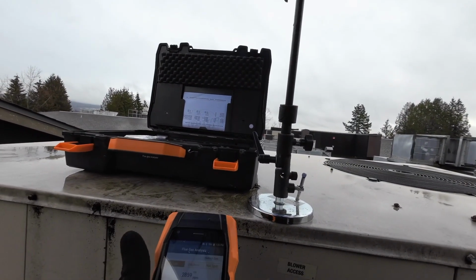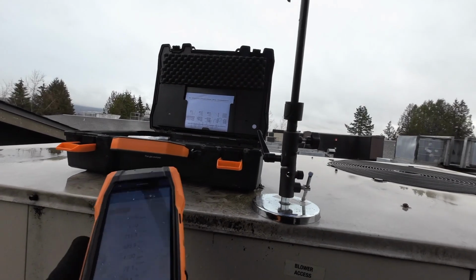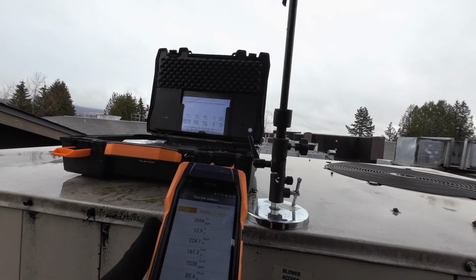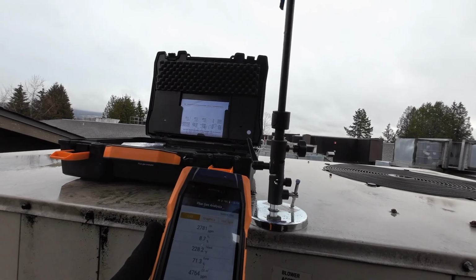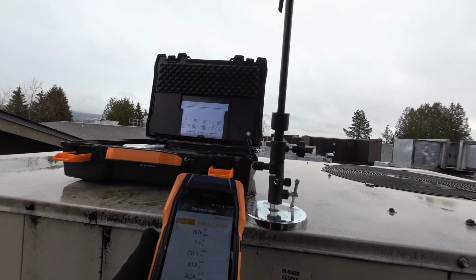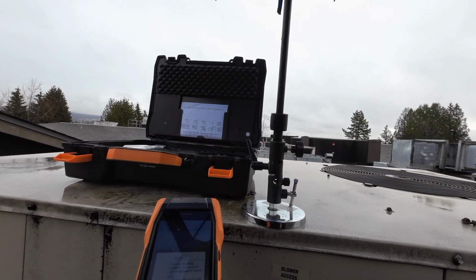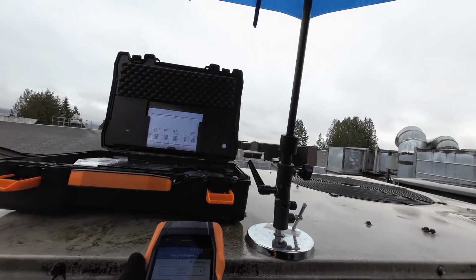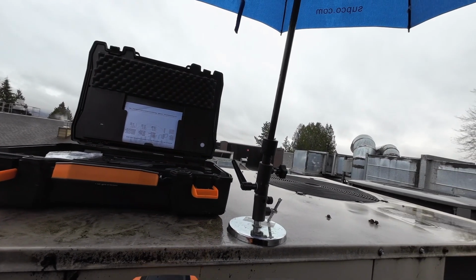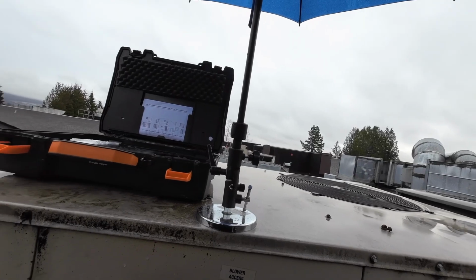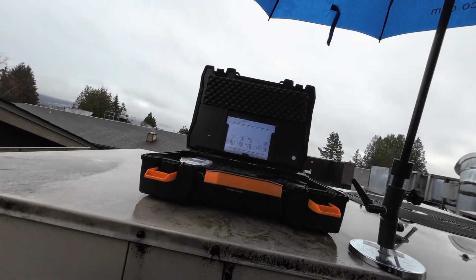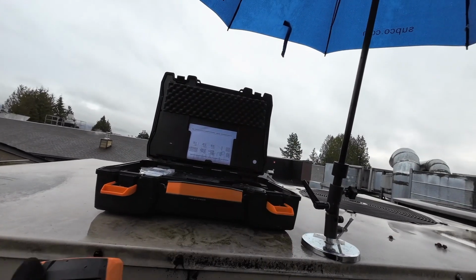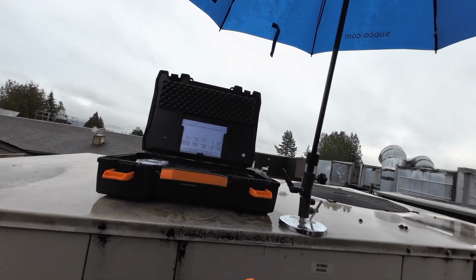How's that for CO? 27 excess air, beyond the threshold. So I've locked out. I've totally locked out. We're at 3,000 parts per million. It's locked out. So gas pressures are good.